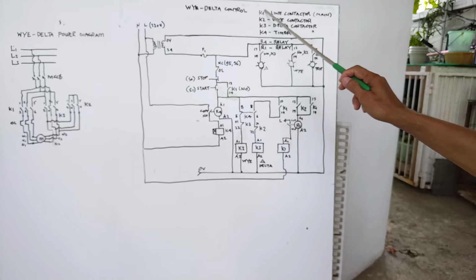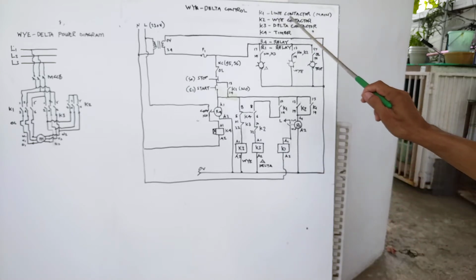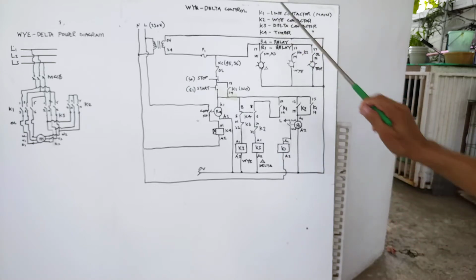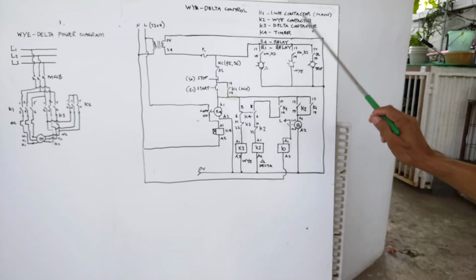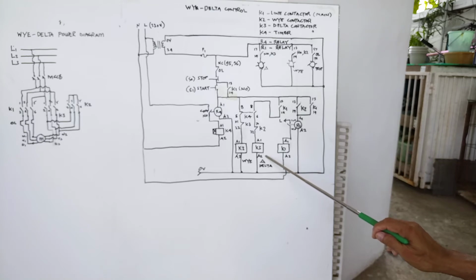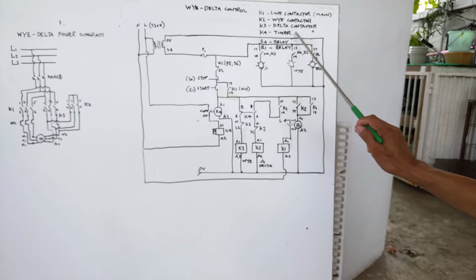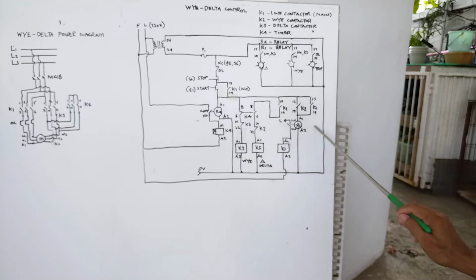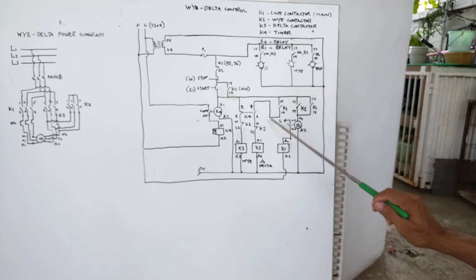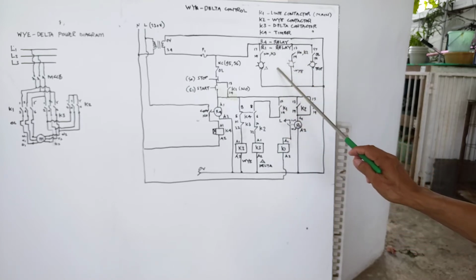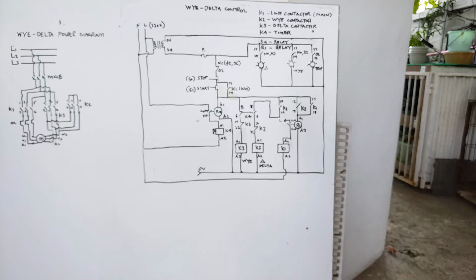First we have the K1, which is our line contactor or main. Then K2, our Y delta contactor, the Y contactor. Then K3 is our delta contactor. K4 is our timer. Then I'm using two relays here, R4 and R1. Then I have my indication lamp. As you can see in my part 1, I tried to simulate the control.